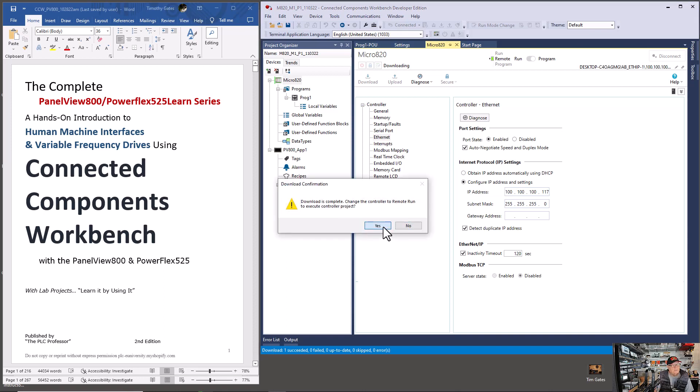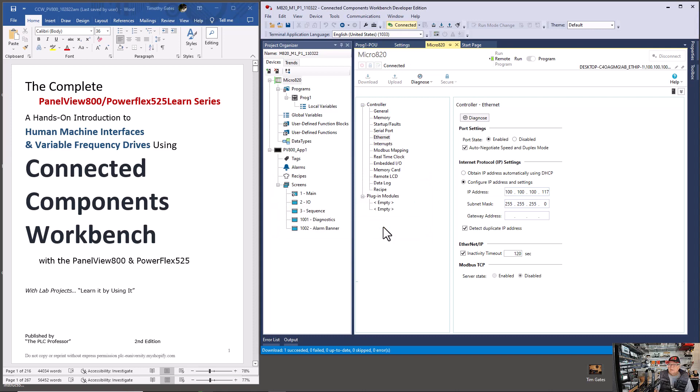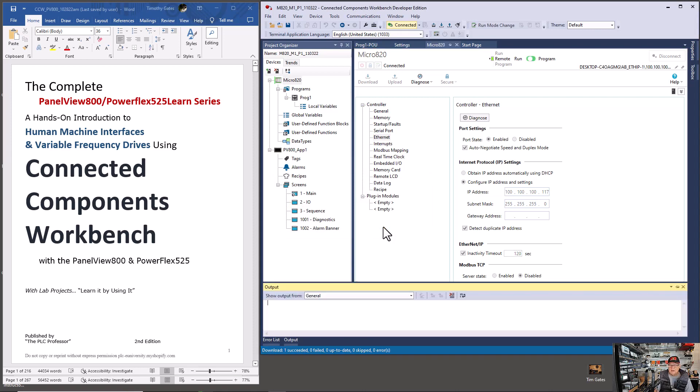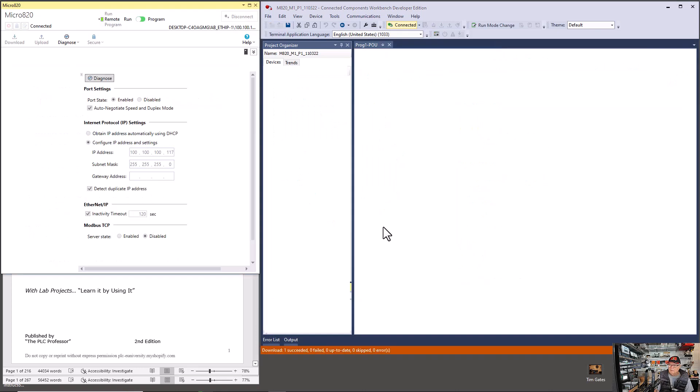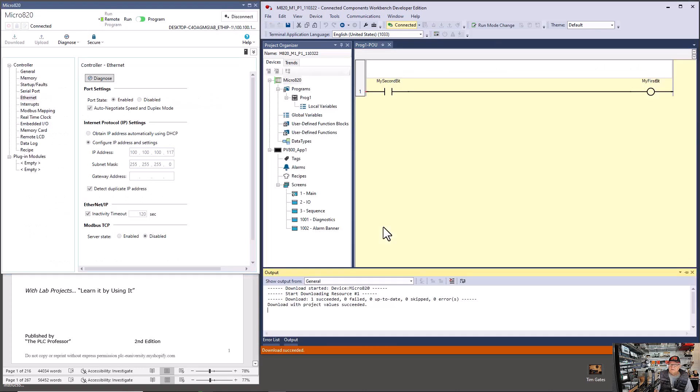Now I'm going to erase the connection path and reconnect it. Now I'm going to download. Download with project values. That's a good habit. There are some circumstances in the field where you don't want to do that. But hopefully by the time you get that far in your learning sequence, you'll know when to do it and when not to do it. Remember you've got data values offline and data values online. You don't want to overwrite your latest data values. We've downloaded and we're now online.